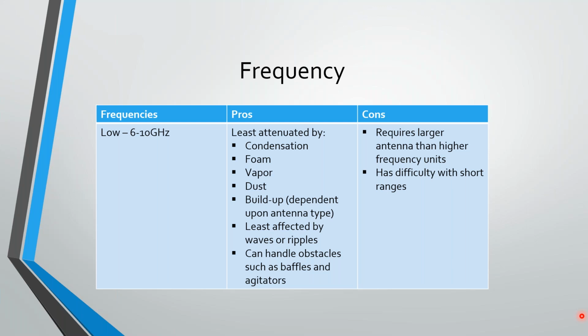It's easy to tune out obstacles such as baffles and agitators. By that, basically, when setting up the device within the electronics, there's something called a snapshot, or sometimes called an empty tank spectrum, where you basically take a picture of it. It's not an actual photo, but electronically the device looks at the empty tank and sees what's there. And what you're saying is, anything that you don't see right now we'll consider to be the level. We're able to tune out things like baffles and agitators, and that's more easily done with a lower frequency device.